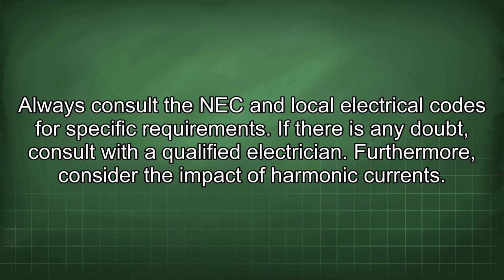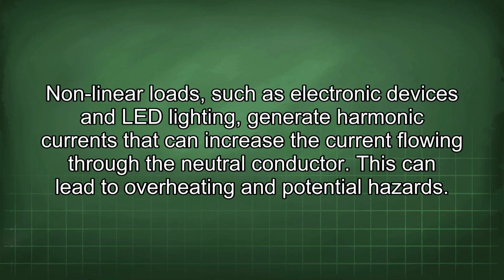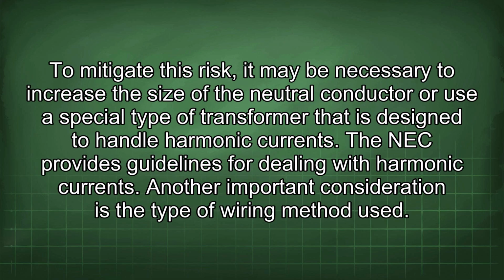Furthermore, consider the impact of harmonic currents. Nonlinear loads, such as electronic devices and LED lighting, generate harmonic currents that can increase the current flowing through the neutral conductor. This can lead to overheating and potential hazards. To mitigate this risk, it may be necessary to increase the size of the neutral conductor or use a special type of transformer that is designed to handle harmonic currents.